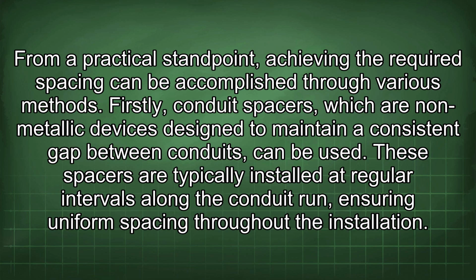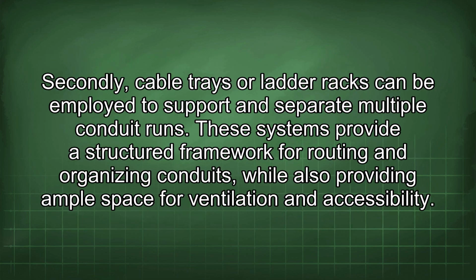From a practical standpoint, achieving the required spacing can be accomplished through various methods. Firstly, conduit spacers, which are non-metallic devices designed to maintain a consistent gap between conduits, can be used. These spacers are typically installed at regular intervals along the conduit run, ensuring uniform spacing throughout the installation. Secondly, cable trays or ladder racks can be employed to support and separate multiple conduit runs. These systems provide a structured framework for routing and organizing conduits, while also providing ample space for ventilation and accessibility.